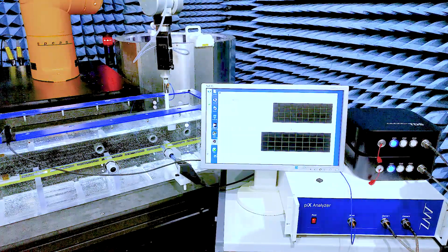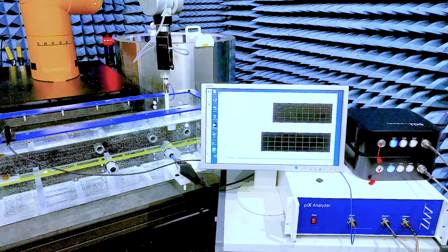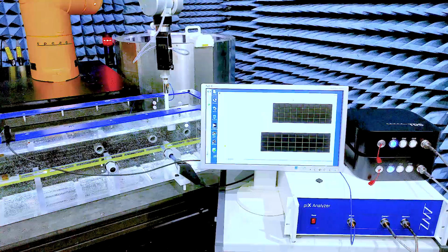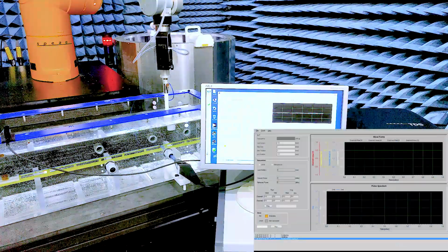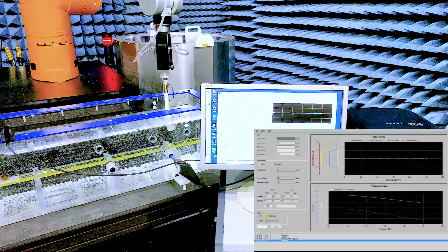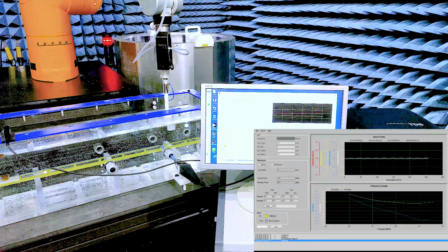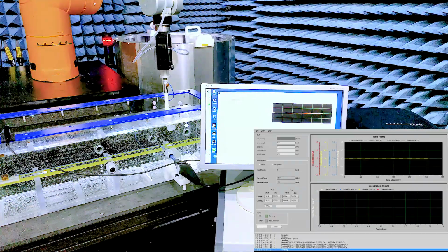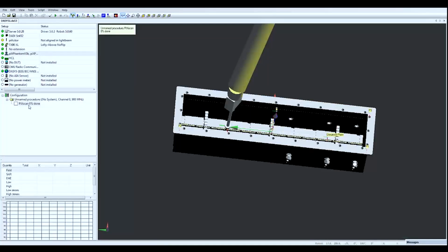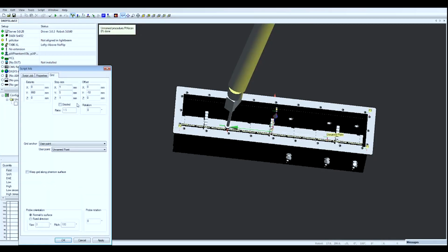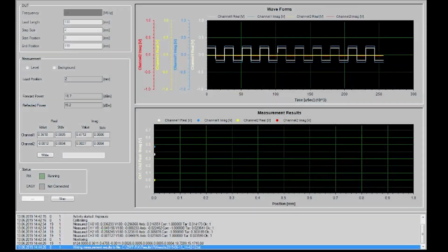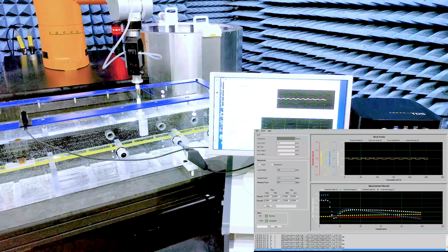The piX system is connected to the DASY software so that the DASY system can position the exciter at each step, and then the piX can automatically capture both data points. First, we run the piX software installed on the piX analyzer's computer, which will initialize the exciter and start radiating. Then we open the DASY software to create a job with the piX script. We tell the DASY the length of our device and the measurement step size. Let's use 5 millimeters today. Now we start the piX job we just defined, and everything will work automatically. The measurement is done in just a couple minutes.